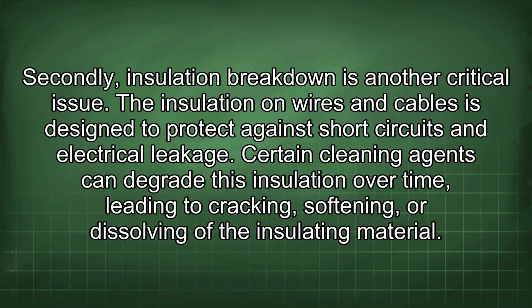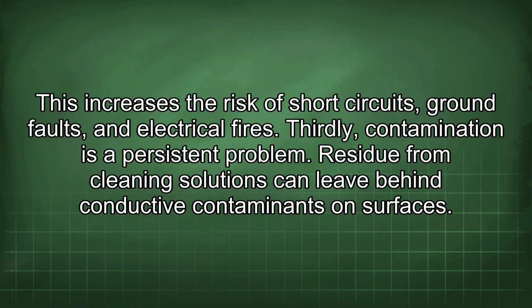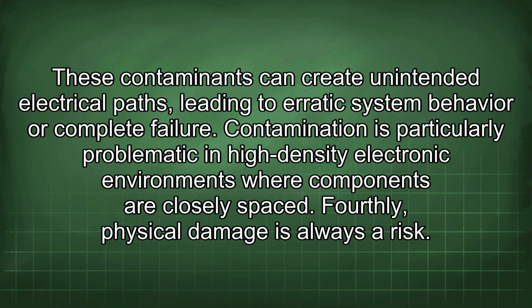Secondly, insulation breakdown is another critical issue. The insulation on wires and cables is designed to protect against short circuits and electrical leakage. Certain cleaning agents can degrade this insulation over time, leading to cracking, softening, or dissolving of the insulating material. This increases the risk of short circuits, ground faults, and electrical fires. Thirdly, contamination is a persistent problem. Residue from cleaning solutions can leave behind conductive contaminants on surfaces. These contaminants can create unintended electrical paths, leading to erratic system behavior or complete failure. Contamination is particularly problematic in high-density electronic environments where components are closely spaced.